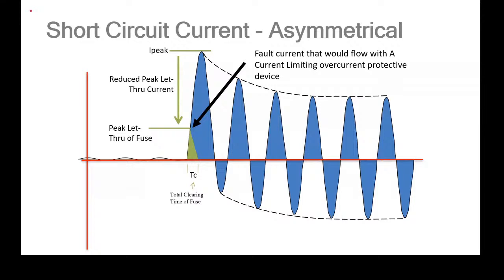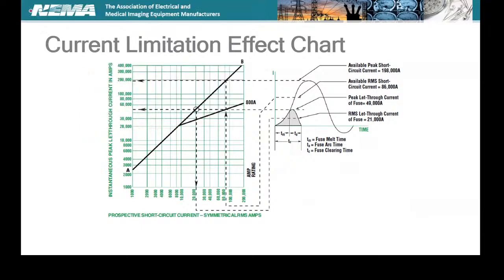Your fuses, they love current. They eat current for breakfast, lunch, and dinner. The more of it, the more they love it, and the faster they'll go. So you limit the amount of time you let that current flow, but you also limit that peak current. So your equipment might say it's 100,000 amps, but in reality, because the fuse is doing its job, it's nowhere near 100,000 amps that your electrical equipment will see. It'll only see a peak current that is much less and much less duration. And this chart tells you the performance of those fuses for those very high currents when they go into the current limiting region.